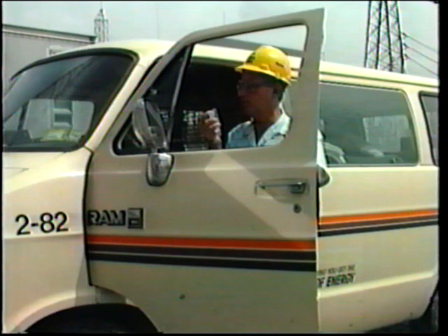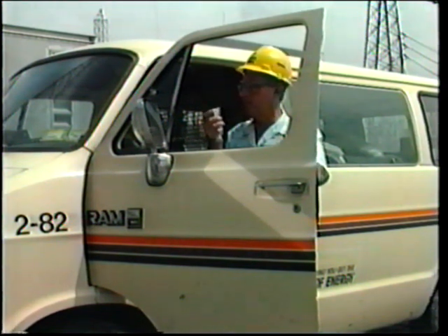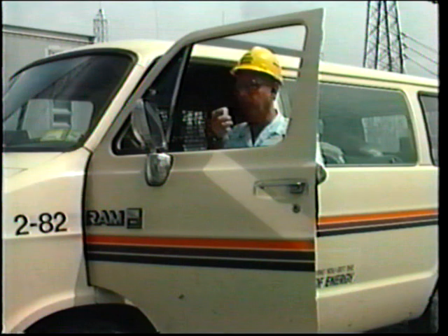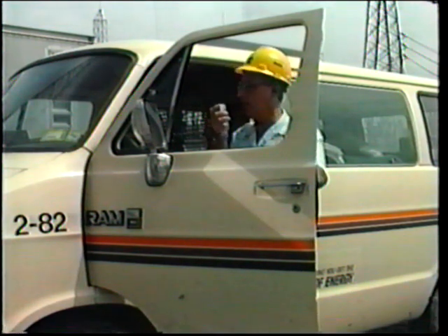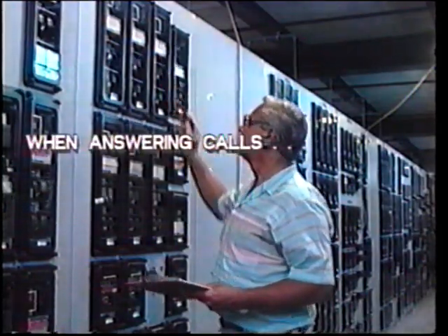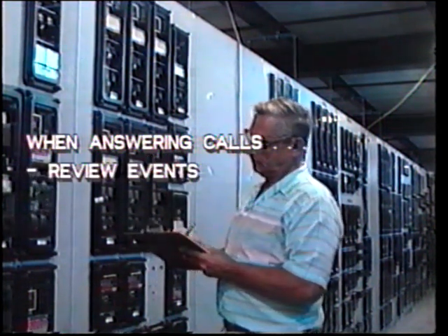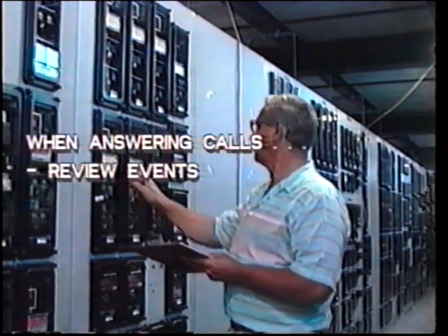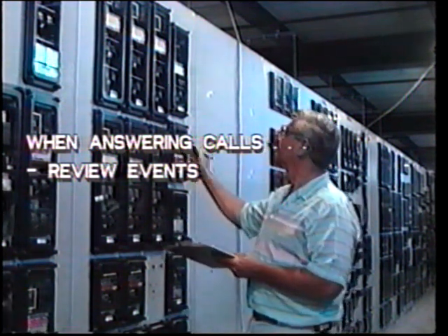Up to this point, we've been dealing with pre-planned inspection and testing of protection equipment. But relay technicians are often called in to investigate trouble. A trouble call to a relay technician will usually be the result of an alarm or a system fault or misoperation of protection equipment. When answering one of these calls, the first thing you should do is to review the events that occurred, such as open breakers, relay targets, annunciator indications, and so on. Make sure that these indications are correctly recorded, especially relay targets.